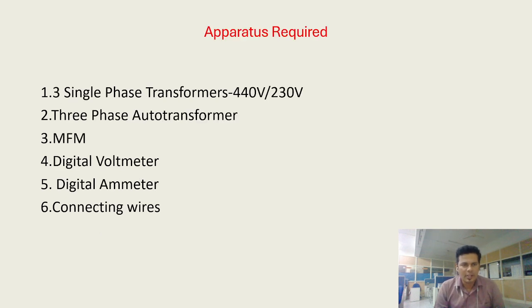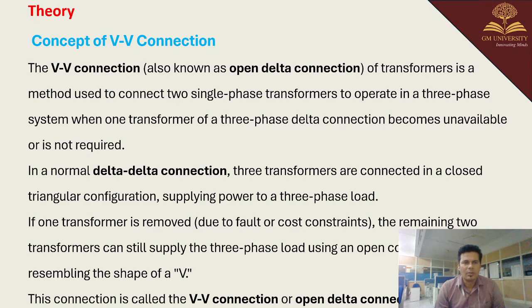The apparatus we require here are 3 single phase transformers, a 3 phase auto transformer, a multifunction meter, a digital voltmeter, a digital ammeter and some connecting wires. When you talk about the theory, the VV connection is also known as the open delta connection of a transformer, which is a method to connect 2 single phase transformers to operate in a 3 phase system when one transformer of the 3 phase delta connection becomes unavailable or is not required.